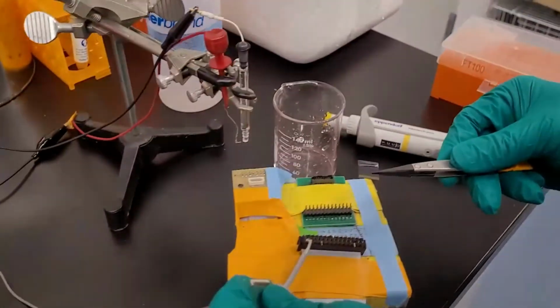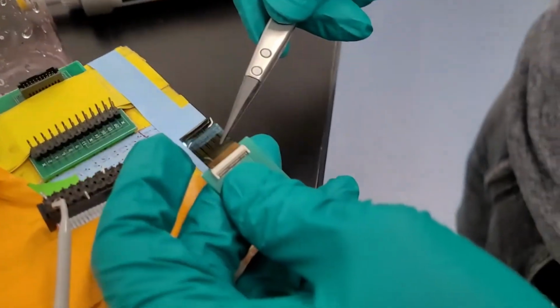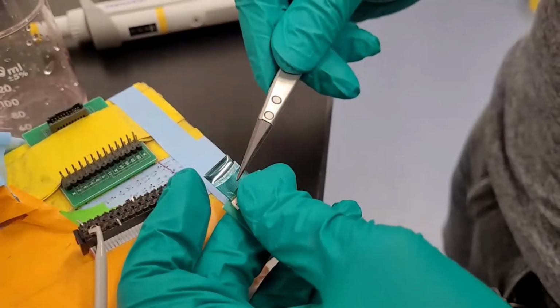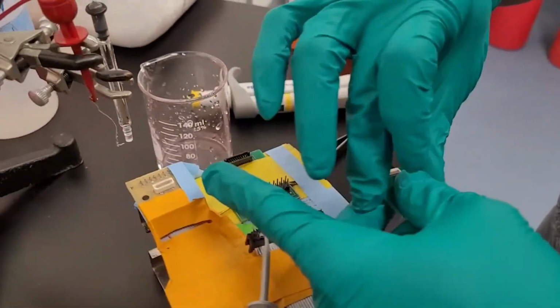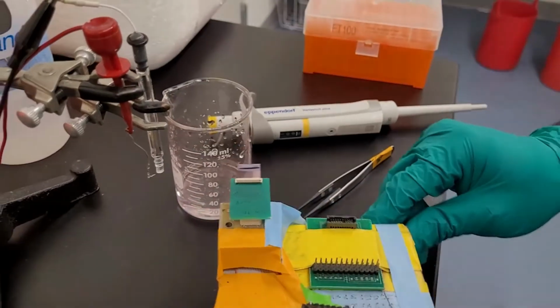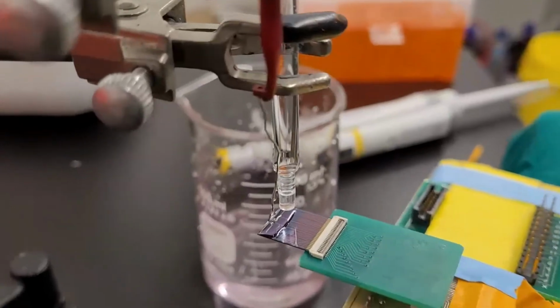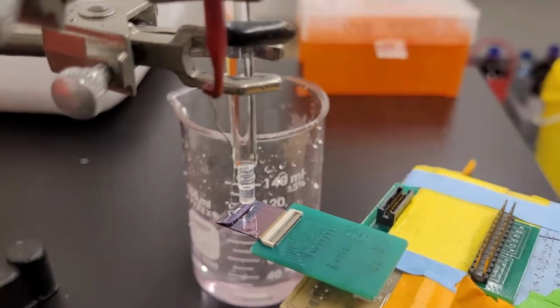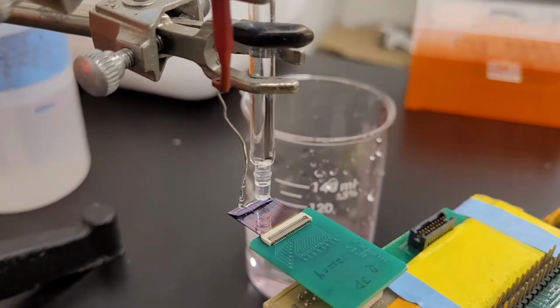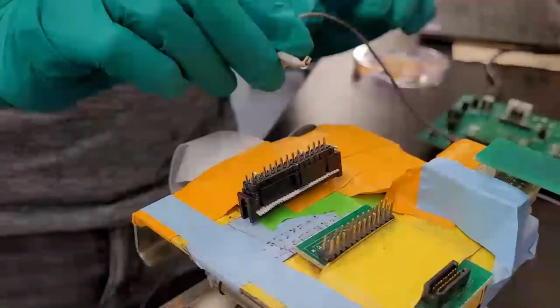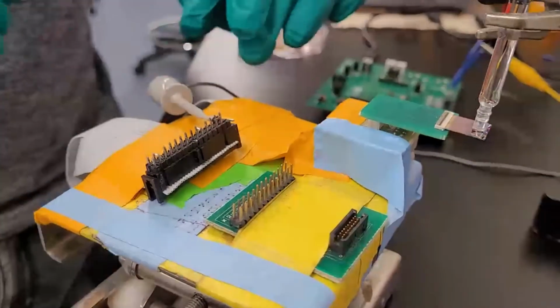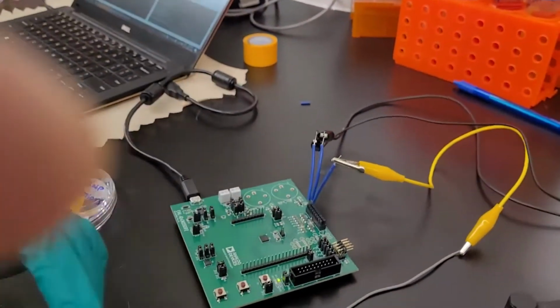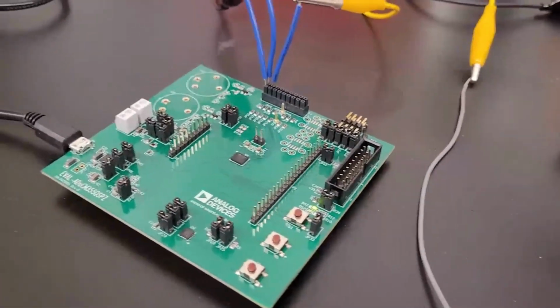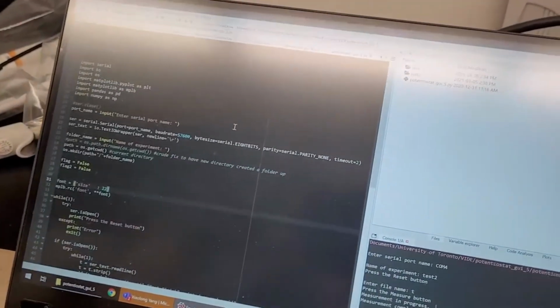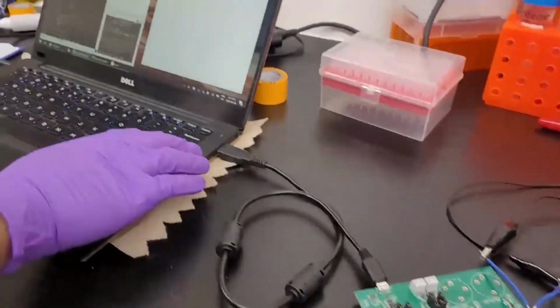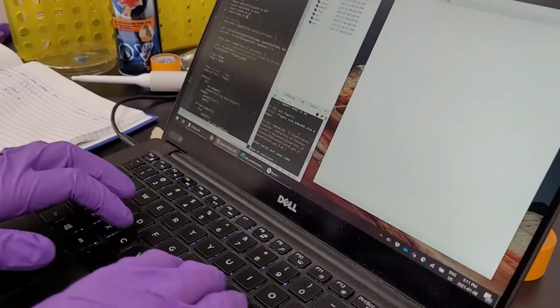So here we take our chip for the experiment, put it into a clamp, as you can see here. This is then put onto our benchtop setup with the breakouts for all the working electrodes, and here you can see we're placing the chip such that the reference and counter electrodes are touching the fluid that is on the chip. And here we take another probe to connect it to one of our working electrodes. And here's the EVAL-ADuCM355 setup we're using, and it's connected to our computer with some in-house software for interacting with it. So here we're doing our measurements.